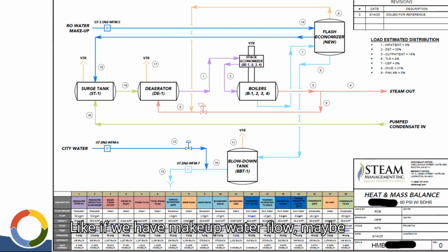This is what I was talking about earlier. If we have makeup water flow, maybe we can determine what the expected condensate flow is. You have to make some assumptions sometimes to finish it out, but you can get a pretty good idea what's going on. You can run different cases, summer case, winter case, or 25, 50, 75, 100% load. Then you can plug in pieces of equipment like blowdown heat recovery and see what the impact on the system is, because some of these savings pull away from other savings. It's a really good tool for us to help develop scopes.